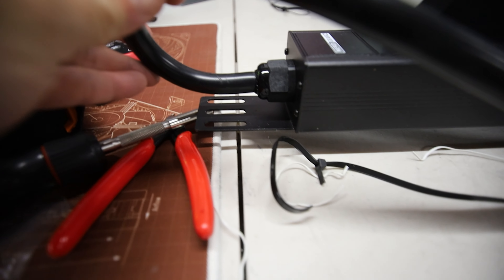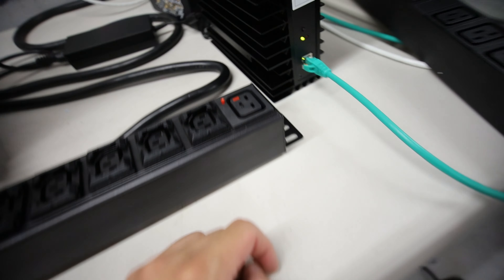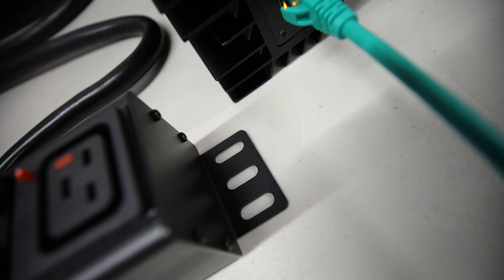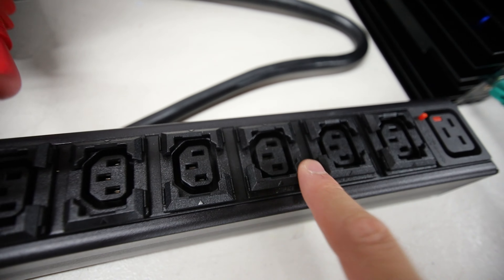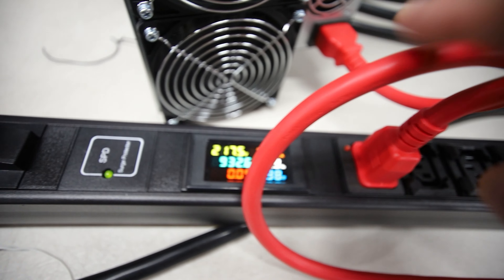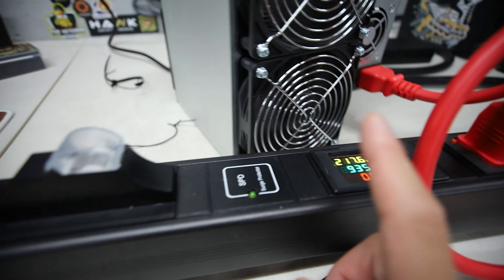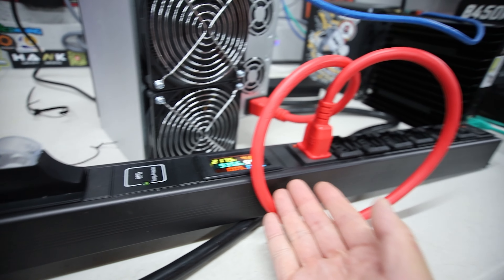I'm drawing about 918 watts. That's the power of having a power meter inside the PDU — you can actually see how much power you are drawing off all your equipment, which is ultimately the best feature of this PDU. A lot of people who buy PDUs really don't know how much they're drawing unless they had an external meter box. This has the DRock meter inside the PDU, which gives it a lot of value.